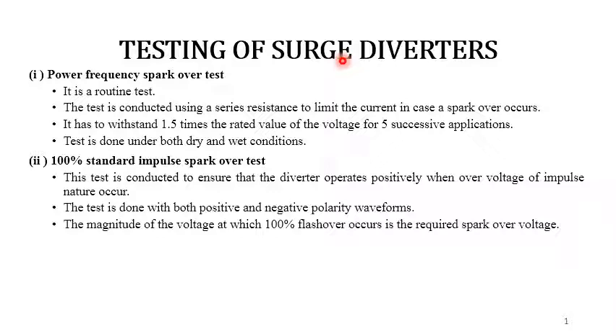There are different tests like the power frequency spark over test, the 100% standard impulse spark over test, the residual voltage test, then the high current impulse test, in that for longer duration of the current pulses, then the operating duty cycle test and other tests. So these are the different tests which you are going to do on the surge diverters. Coming to the first one, that is the power frequency spark over test. This is a routine test.